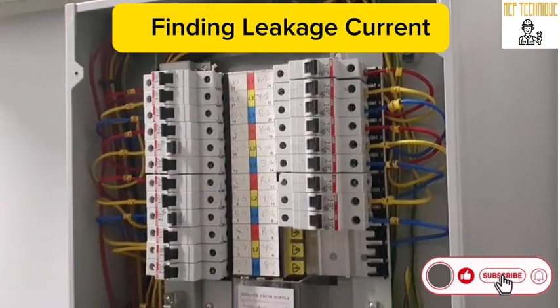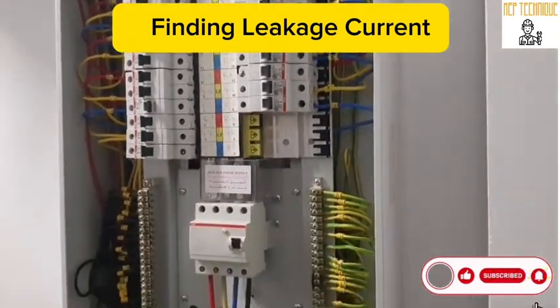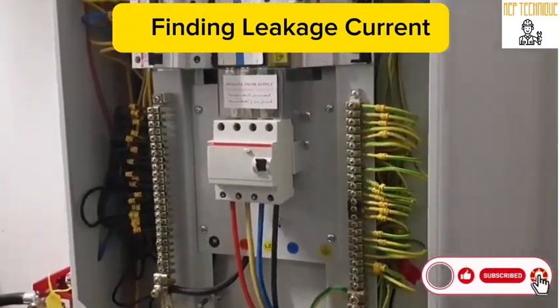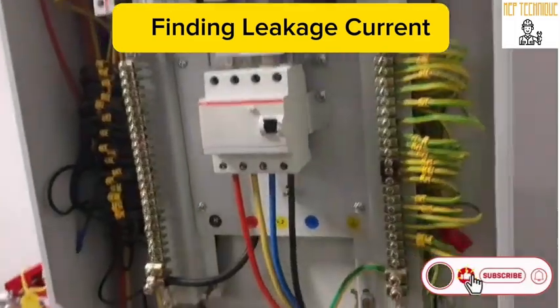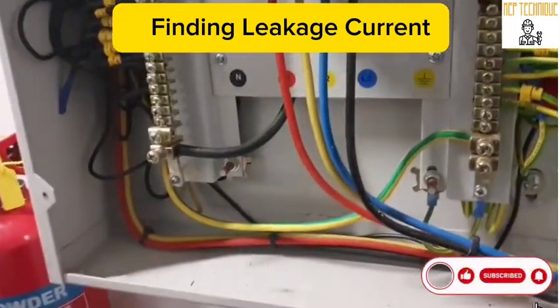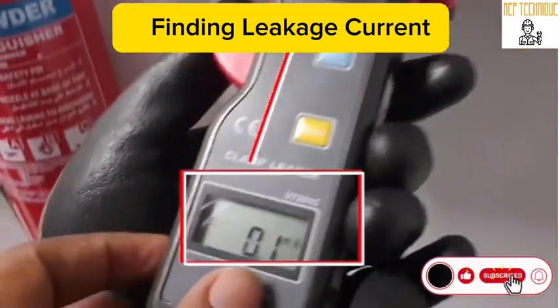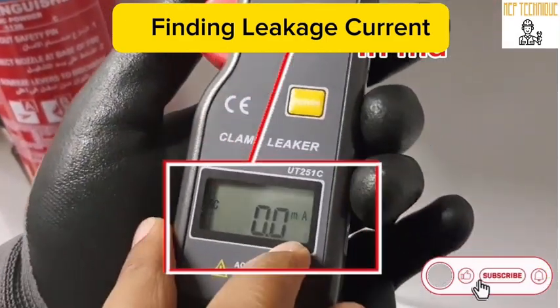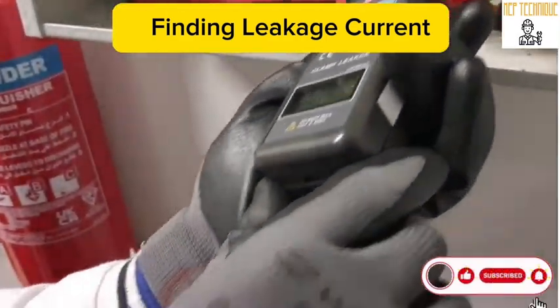Today we are going to check the leakage current of this RCCB by using a clamp leaker, also called a leakage clamp meter. This is the clamp leaker, and you can see the reading showing 0.0 milliampere.